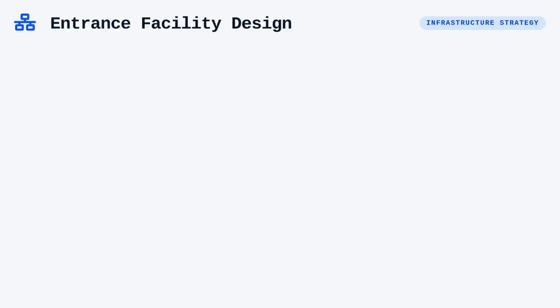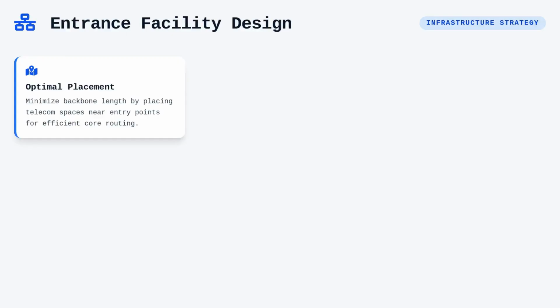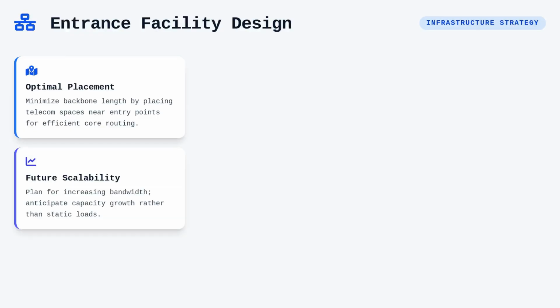Beyond physical protection and grounding, the functional design of the entrance facility must account for accessibility and future scalability. You should consider the placement of telecommunication spaces relative to the entrance point to minimize the backbone length and ensure efficient routing paths through the building core. This involves not only planning the current cabling load, but also anticipating future capacity requirements, as data bandwidth needs typically increase over time rather than remaining stagnant.